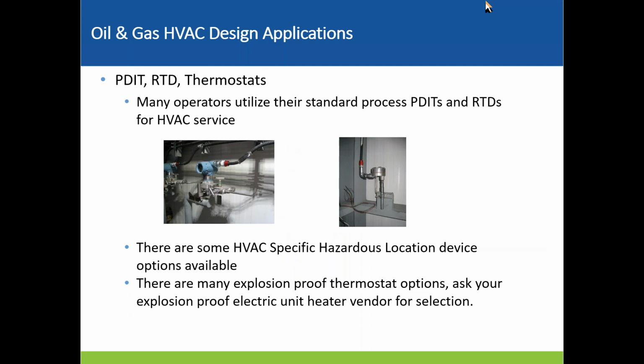Most operators, many operators, I would say most, will typically utilize their own process PDITs and RTDs, pressure differential and temperature devices. These are typically used for process conditions, but because of the way we stock things on the slope and what our instrument techs are used to working on, bringing in HVAC specific devices is not something that's accepted by the instrument engineers on projects. There are some specific HVAC devices available though that are explosion proof. I just haven't seen them.